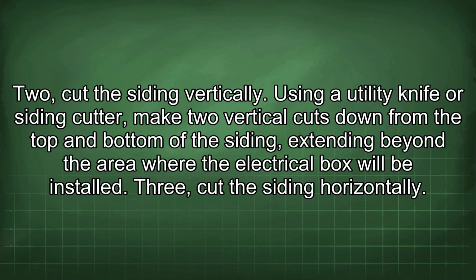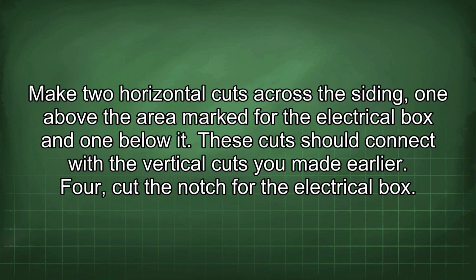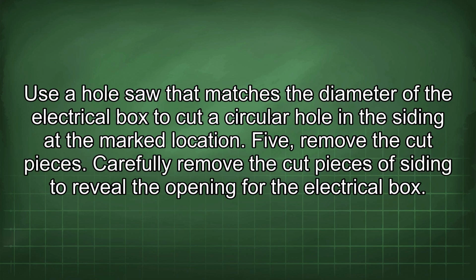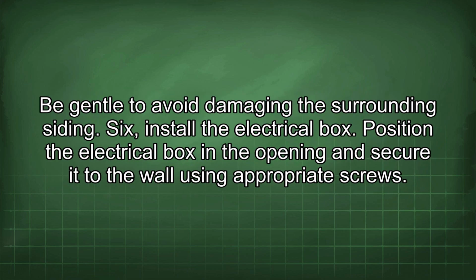3. Cut the siding horizontally. Make 2 horizontal cuts across the siding, one above the area marked for the electrical box and one below it. These cuts should connect with the vertical cuts you made earlier. 4. Cut the notch for the electrical box. Use a hole saw that matches the diameter of the electrical box to cut a circular hole in the siding at the marked location. 5. Remove the cut pieces. Carefully remove the cut pieces of siding to reveal the opening for the electrical box. Be gentle to avoid damaging the surrounding siding.